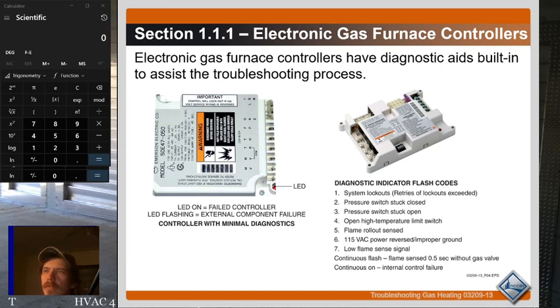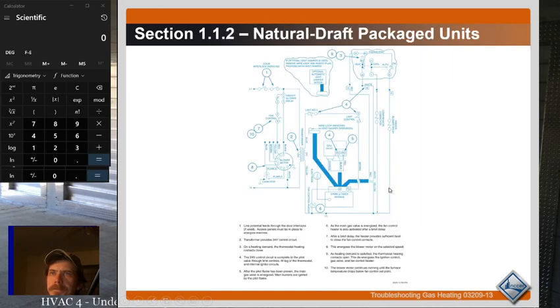So if a furnace isn't working right, generally this is going to be when you first started up or an electrician did some work or something like that. If it's not operating right, you want to verify polarity of the power coming in, because it has to be black to black, white to white, and black has to be hot and white has to be neutral. If it's not like that, you need to reverse black and white so that the polarity is right.